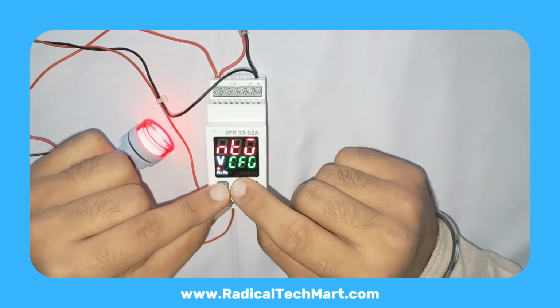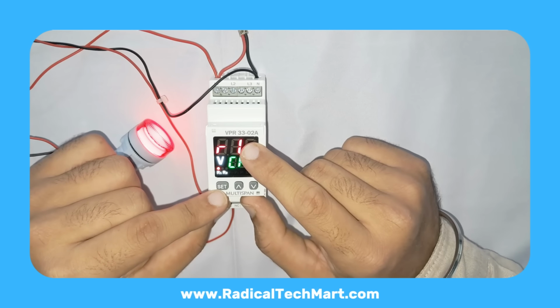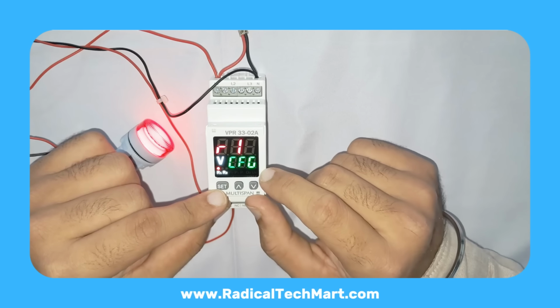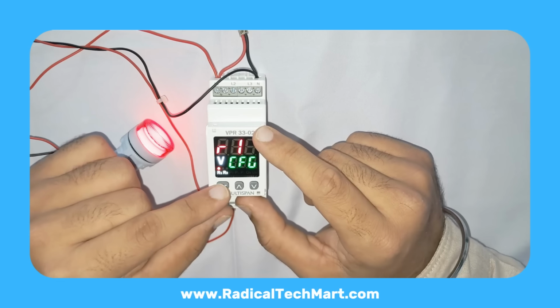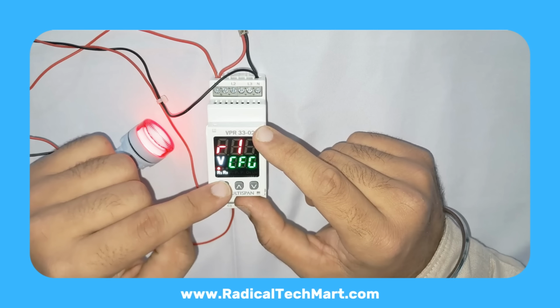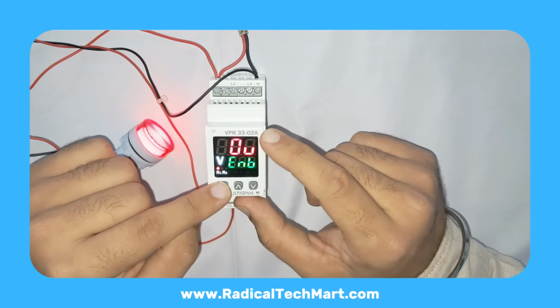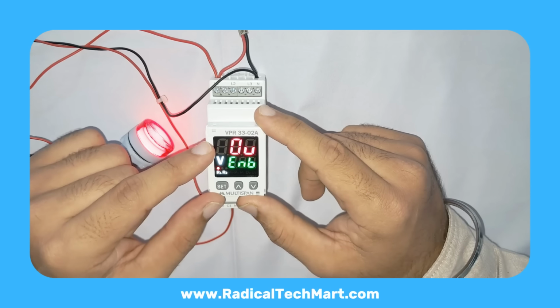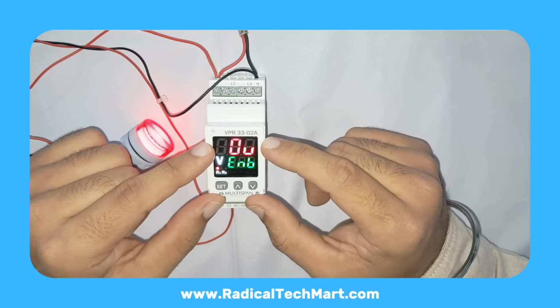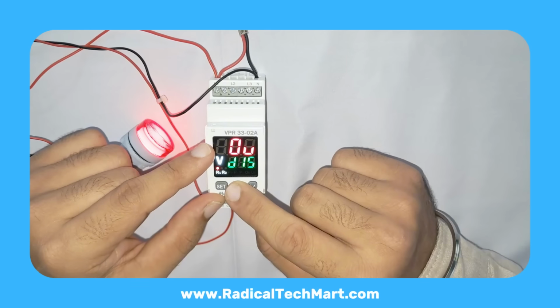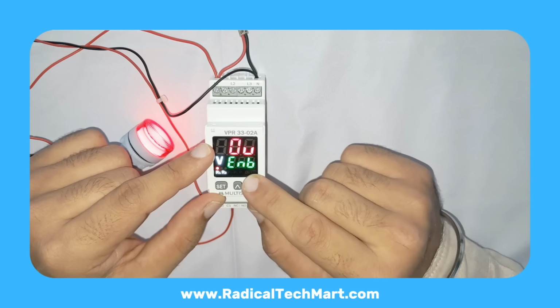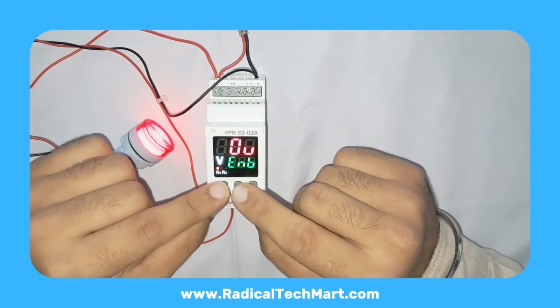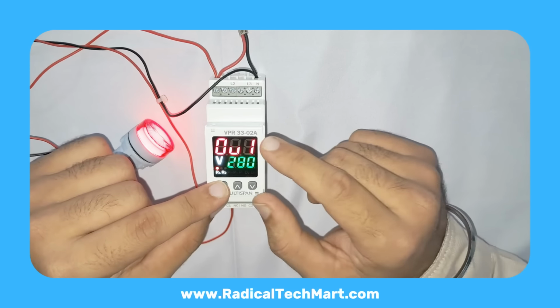Press Set to confirm. Relay 1 configuration, R1 CFG. Press the up button, and you will see R1 on top and CFG below. This is Relay 1 configuration. Press Set to enter. Now we go through each protection parameter for Relay 1. First option, OV, Overvoltage. You can enable or disable it using up-down. We will enable it. Press Set.